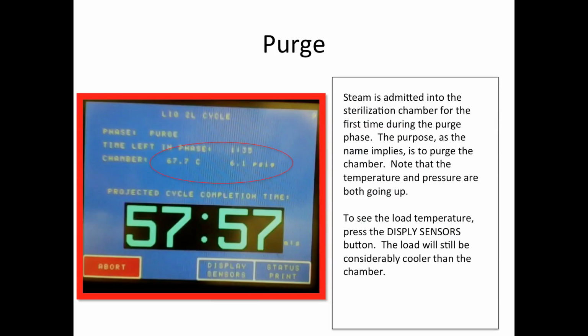And now in the purge phase, we admit steam into the chamber for the first time. The purpose, as the name implies, is to purge the sterilization chamber. And you'll note that both the temperature and the pressure are going up. Now, to see what's actually happening with your load temperature, you can press the display sensors button. You may find that the load is still considerably cooler than the average temperature of the chamber. And the average temperature of the chamber would be this temperature right here.